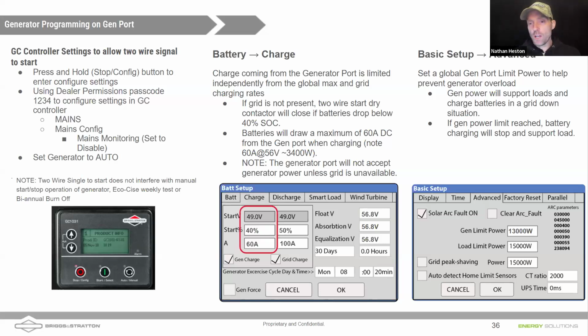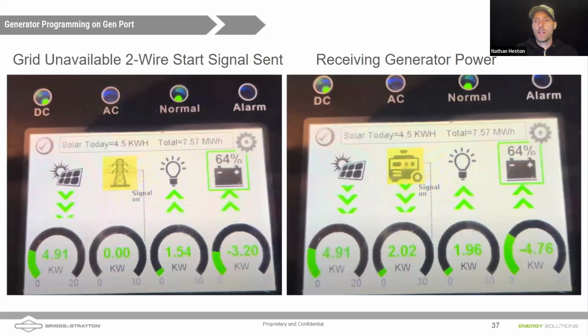If you have a smaller generator, or if you're concerned about that, you can go into the Basic Setup Advanced tab and set a gen limit power, right? What you see on the screen in the bottom right-hand corner is we've programmed in 13,000 watts there. So we limit the amount of power that we will pull from the gen port to that. And if you go over that amount of power because your loads get high and you are charging too fast, it should reduce your charge rate to not exceed that 13,000 watts you've programmed in there. So it's a helpful feature. Another reason I like Sol-Ark is having all of these settings available.